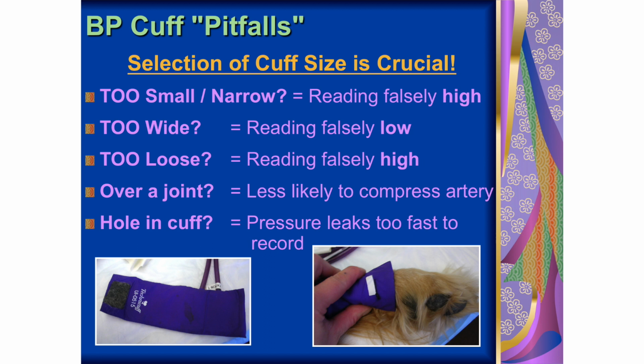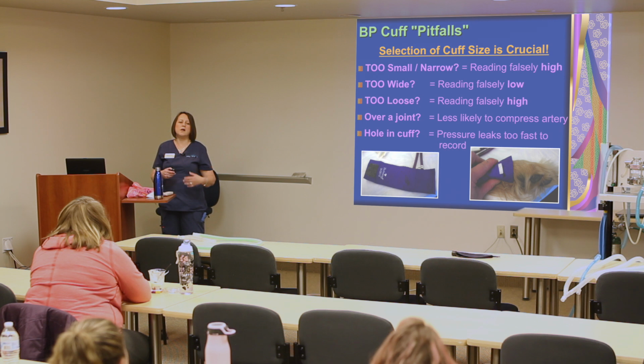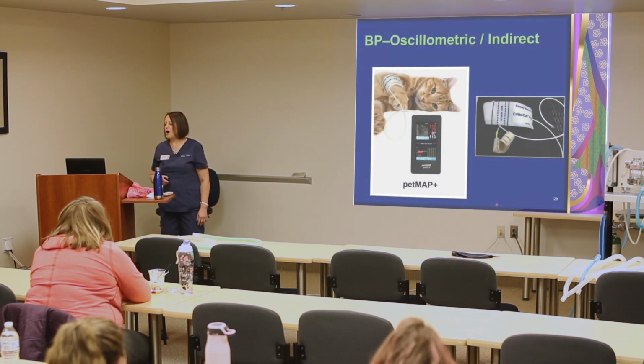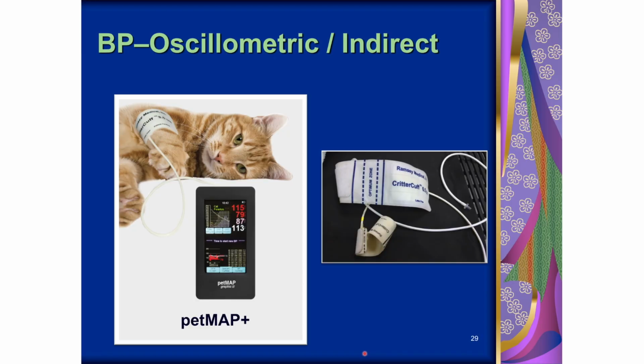So we have a poster similar to this hanging in the operating room so that we know how important it is to have the correct blood pressure cuff size. And here we do have the petMAPs, which are really popular. They have very specific cuff marks on those. So ideally, this dashed mark right here, the index, should fit within this optimum zone and absolutely cannot go outside of these dark lines. If this mark was going outside of these lines, you would 100% need to choose another cuff.